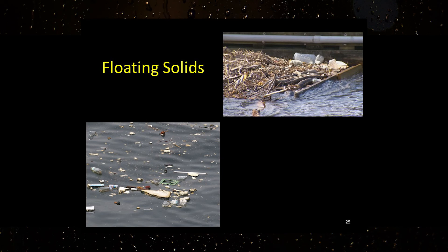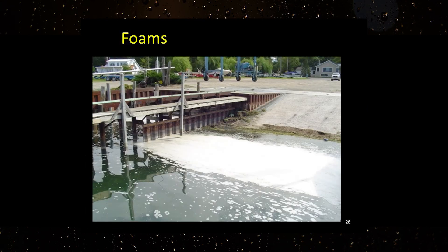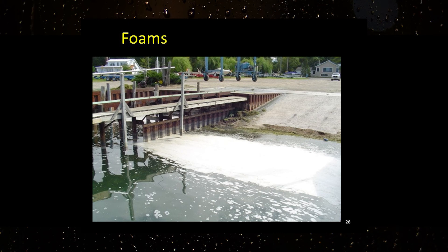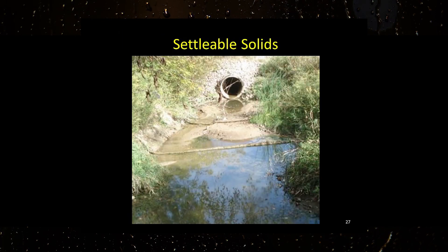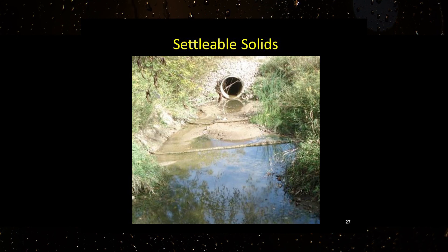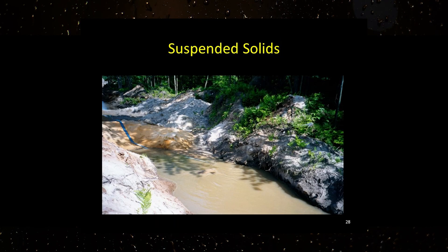Floating solids associated with industrial activity can indicate housekeeping issues and will often be deposited at the outfall or around a discharge point. Unnatural Foams: When organic substances fall into the water and begin to decay, they release compounds known as surfactants, which allow air to more easily mix with water and create bubbles, causing natural foams. Unnatural foams are formed when there are contaminants acting as surfactants and should be documented. Settleable solids are larger in size with greater density and will settle out of the water quickly, resting on the bottom of the container within a few minutes. Suspended solids are smaller in size, which allows them to stay in suspension longer and will be more challenging to manage.